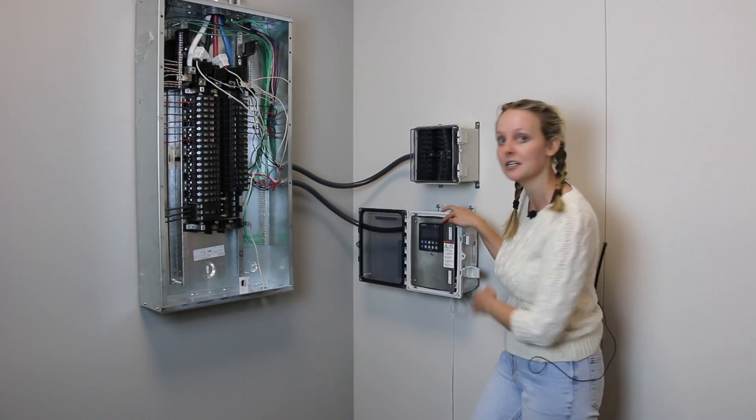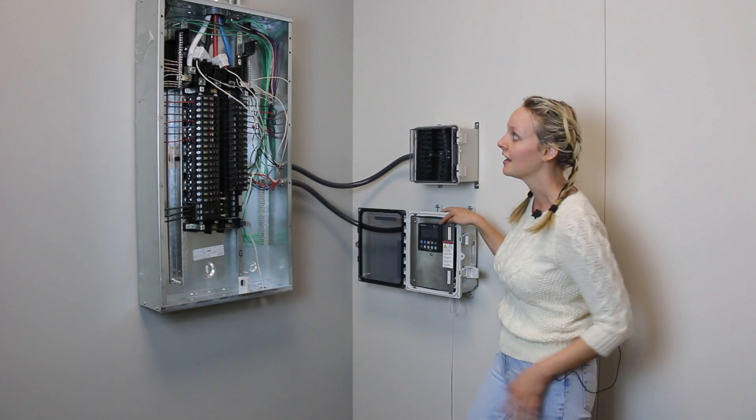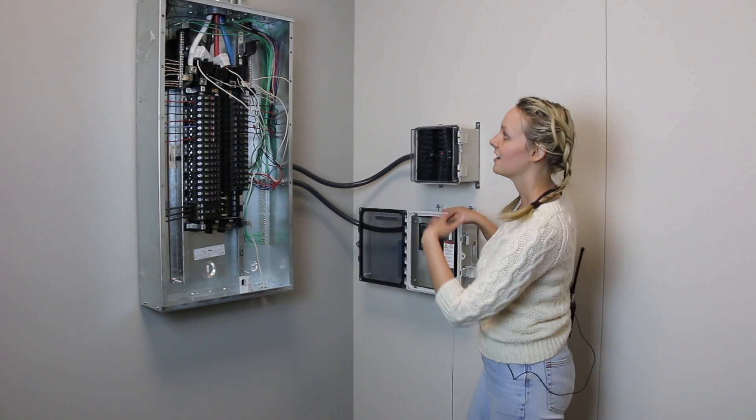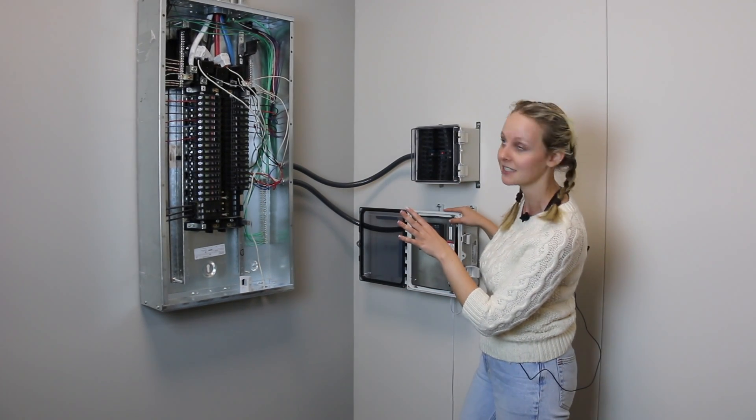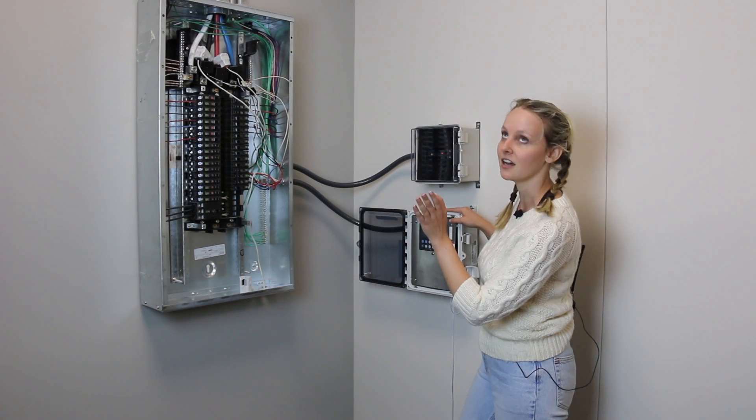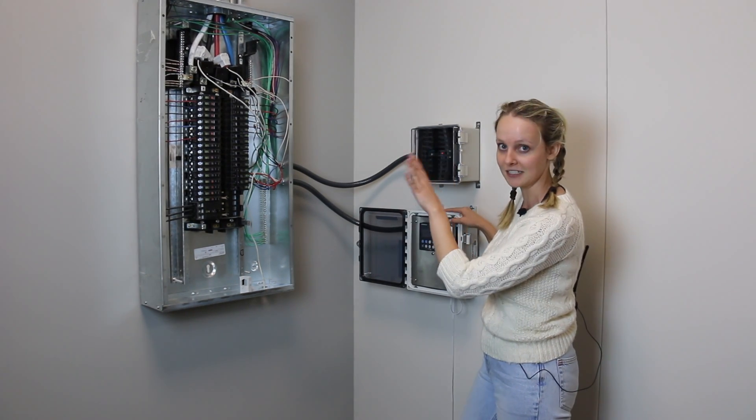As far as accuracy, the meter itself is 0.2 class and what's really great about this is the entire system is 0.5 class from 2% to 120% of the CT rating.